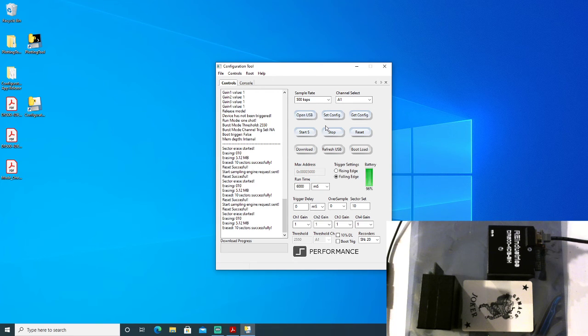So these devices can be embedded in a larger system or device under test and stored for a period of time with power off, and then when the device under test is ready to operate, upon the opening of this jumper, the device will power up, and the auto trigger capability allows the device to run fully autonomously if customers have no access to any of these interfaces here on the front of the recorder. So we'll stick with our 6 seconds. We'll check the boot trigger box, set our configuration, reset, and we can see our boot trigger is true. So now we're ready to go.